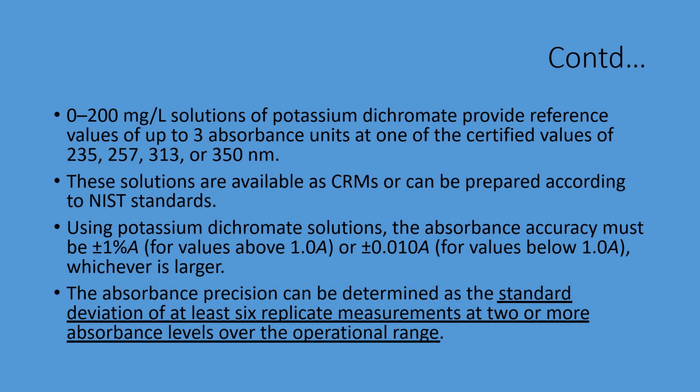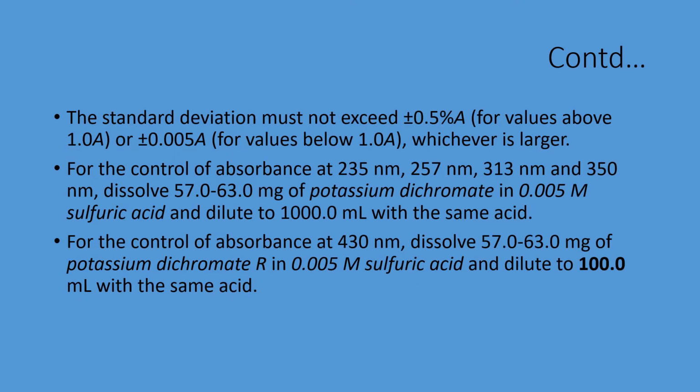So, as a statistical requirement, the measurements from 6 replicates have to be considered for evaluation. The standard deviation must not exceed plus or minus 0.5% of absorbance for values above 1.0 absorbance, or plus or minus 0.005 absorbance units for values below 1.0 absorbance, whichever is larger.